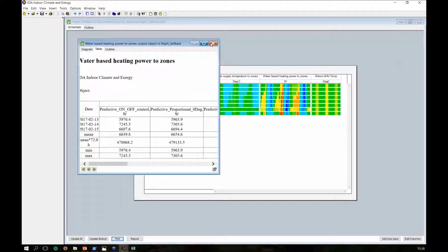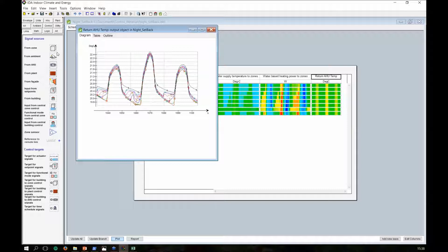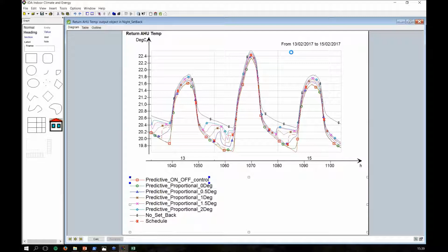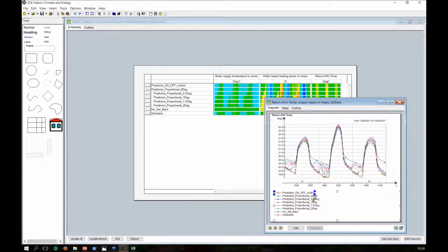We can log the return temperature of the air handling unit, and see here that with no setback, at 8 o'clock, we're reaching around 20.6, 20.8 degrees when the people start to come in at 8 o'clock in the morning. And when we have the predictive on and off control, it's 20.6, 20.5. So it's a 0.2 degree difference in mean air temperature. So maybe that's an okay compromise for us. That is something up to the designer to decide. But what I wanted to show is that night setback works. It's usually an underappreciated control strategy, and you can do nifty things. You can do these predictive controls quite easily in IDA.